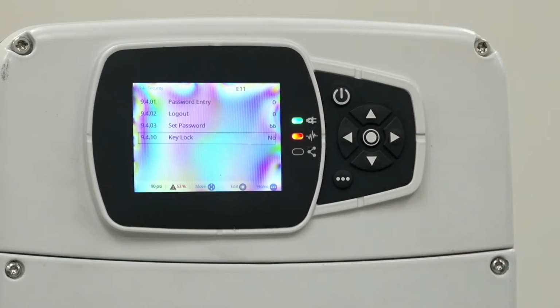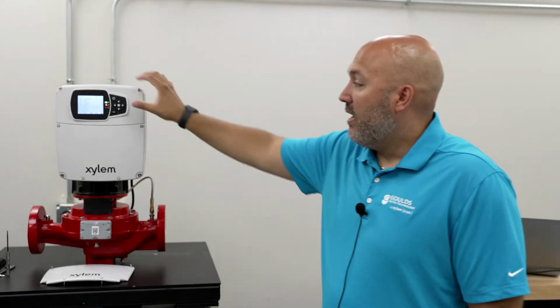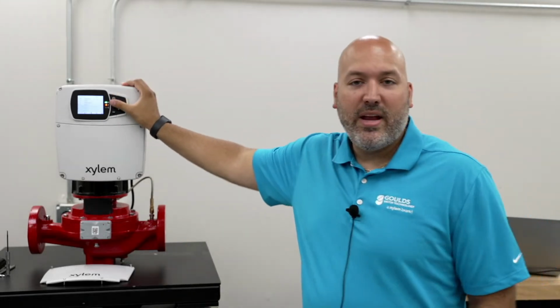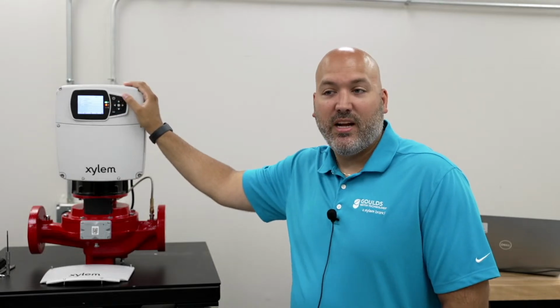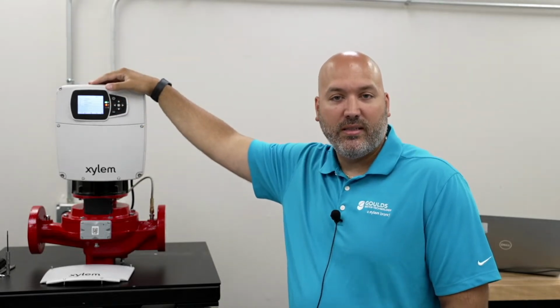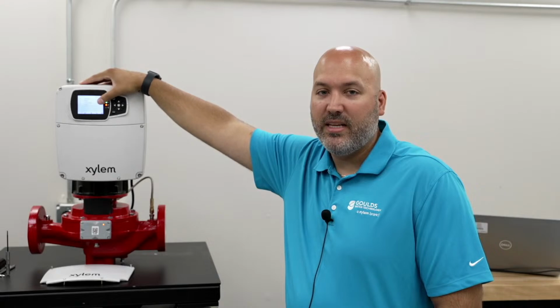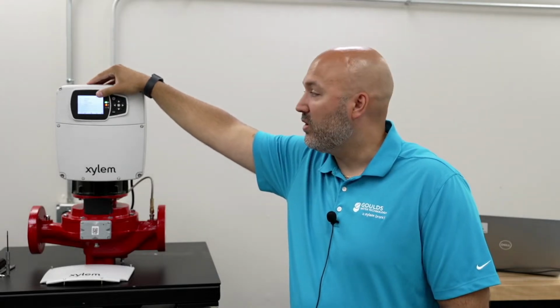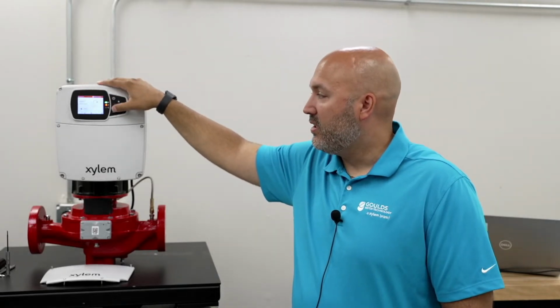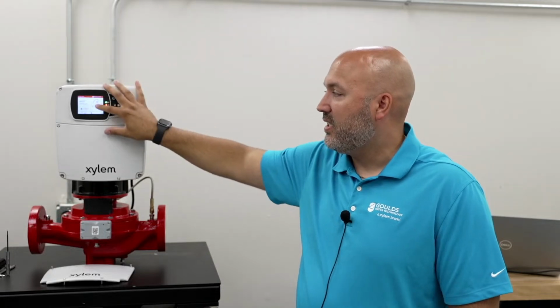An additional question, which is an extension of the enclosure question. Do you need to oversize if mounting in direct sunlight? Yeah, it's all about ambient temperature rating. So if you're exceeding 122 degrees Fahrenheit, that's the max capability of the VFD, then you would need to start to oversize there. The only concern also with direct sunlight is actually the screen itself.